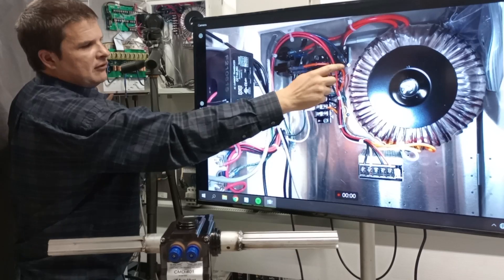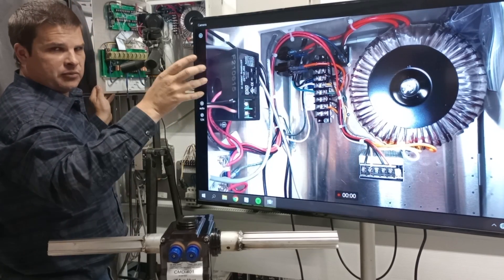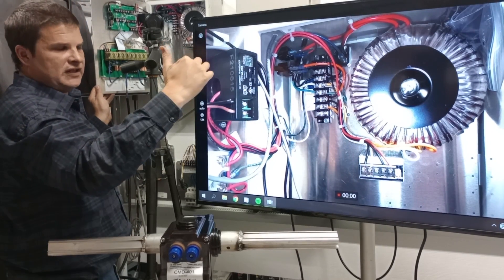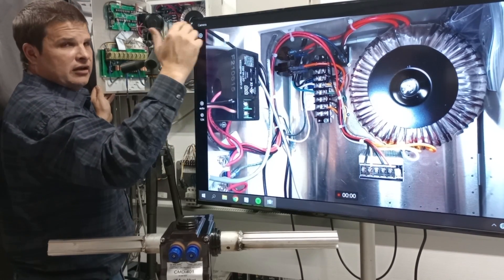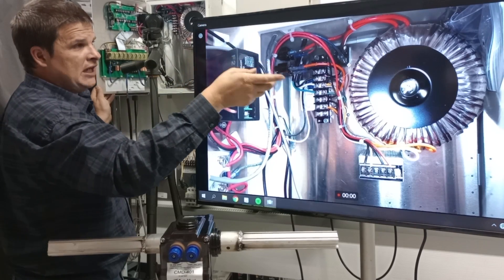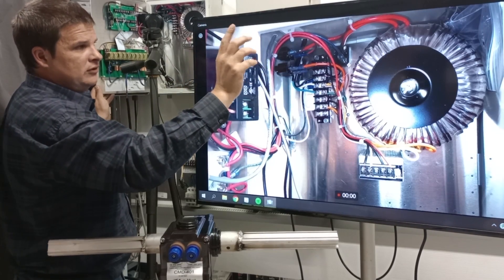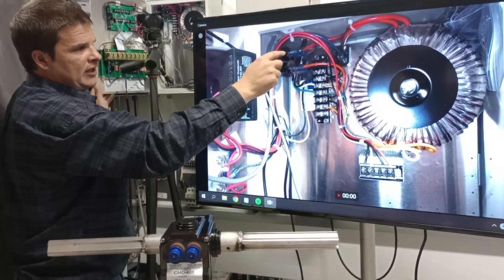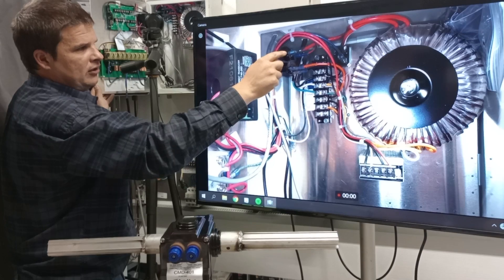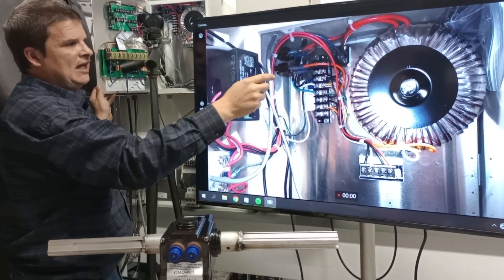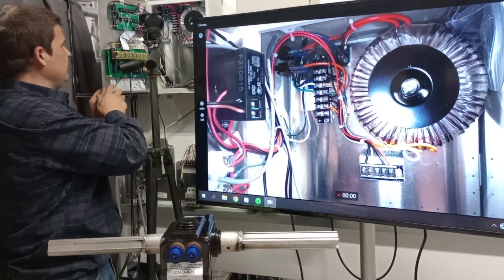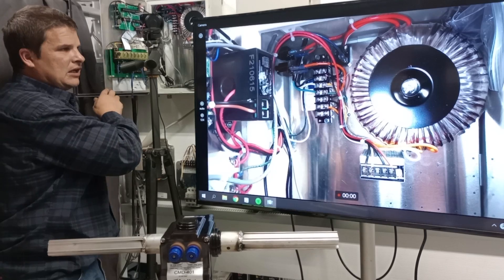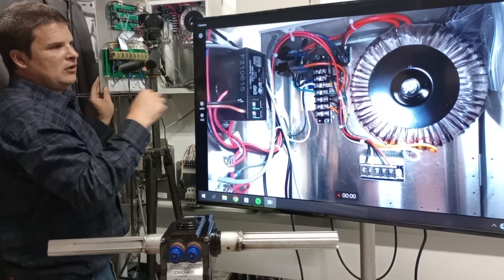This little block right here is a bridge rectifier that converts it to DC. And if that thing goes out, it'll blow these breakers. So right here, we've got a breaker. This is a 20 and a 5. And you reset them from the outside of the box.